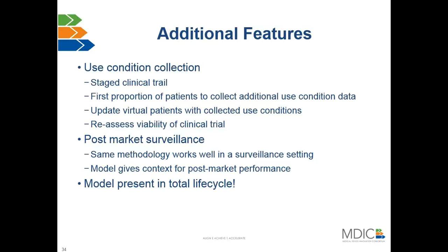So in the case of a stent, you would X-ray the stent in the patient to see how the stent is reacting, or in the terms of leads, you would see how the lead is interacting, and then you'd be able to update your model based off of the true use condition or input data. And that would actually be very beneficial. And it's very cost efficient, because then the patients in the trial are not just being used for the outcome, but they're also being used for the inputs, and that's cost effective.